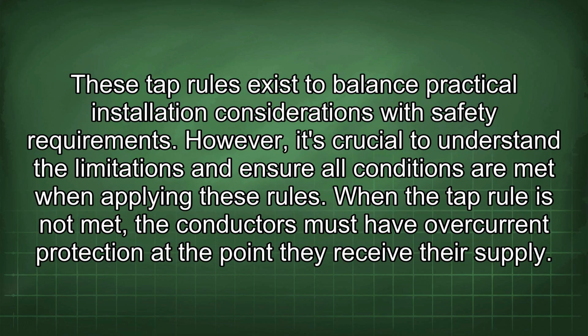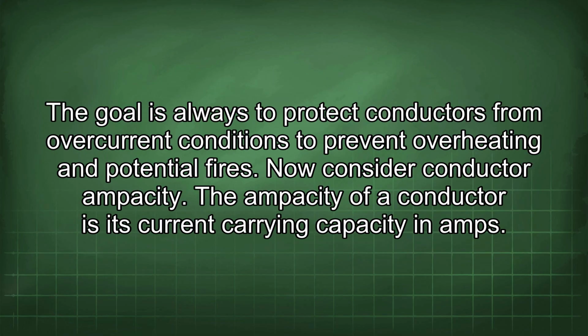These tap rules exist to balance practical installation considerations with safety requirements. However, it's crucial to understand the limitations and ensure all conditions are met when applying these rules. When the tap rule is not met, the conductors must have overcurrent protection at the point they receive their supply. The goal is always to protect conductors from overcurrent conditions to prevent overheating and potential fires.